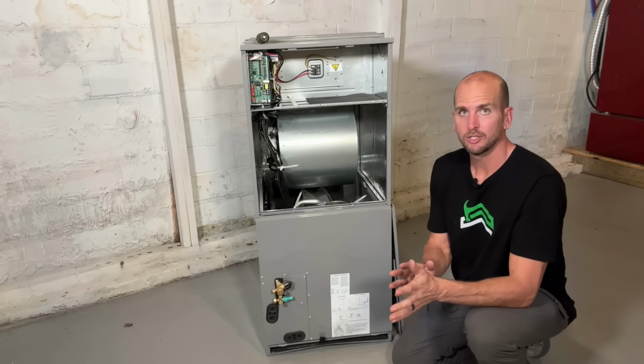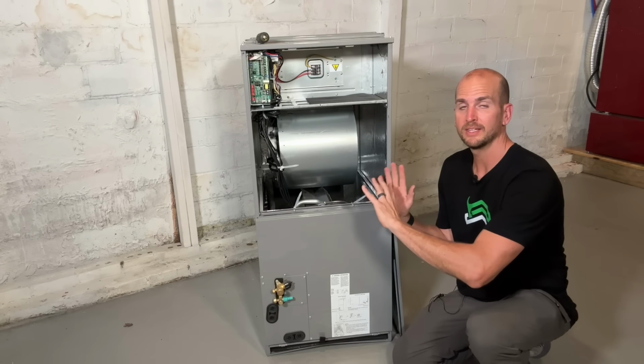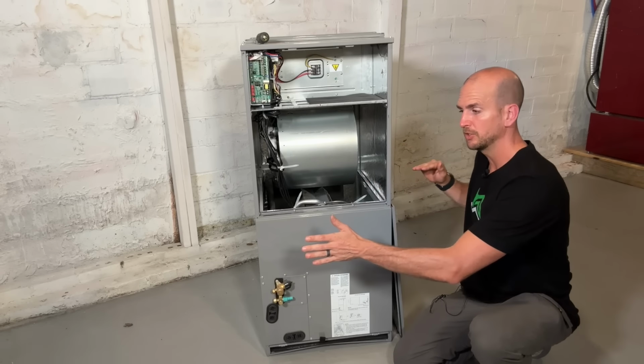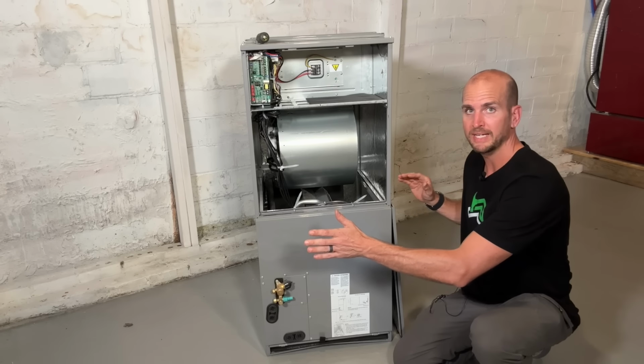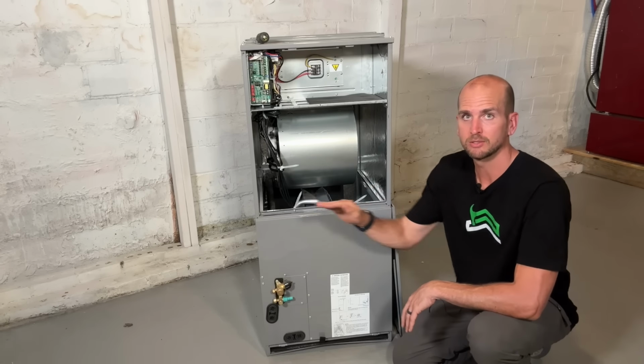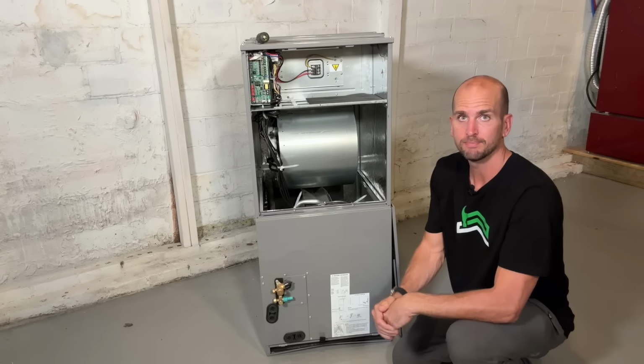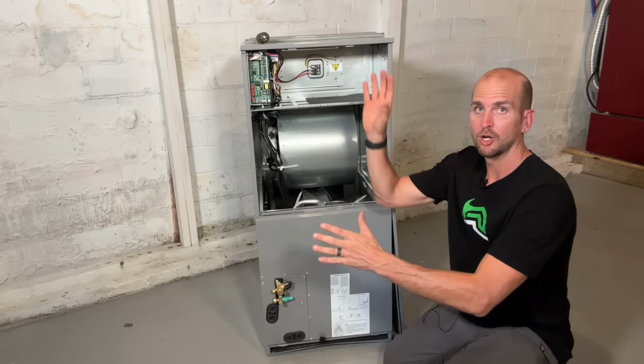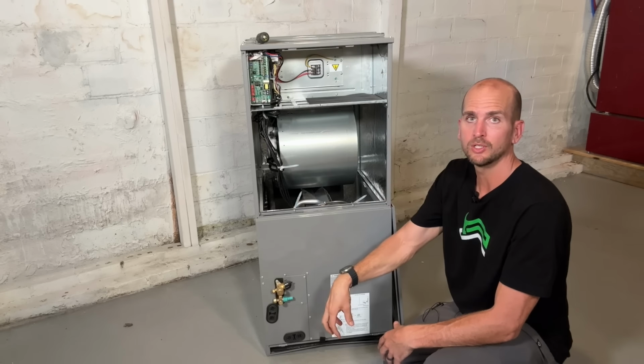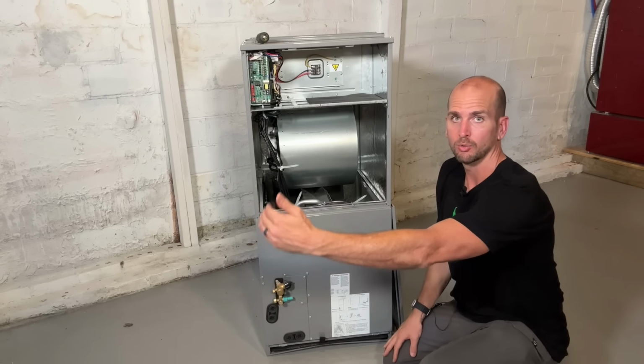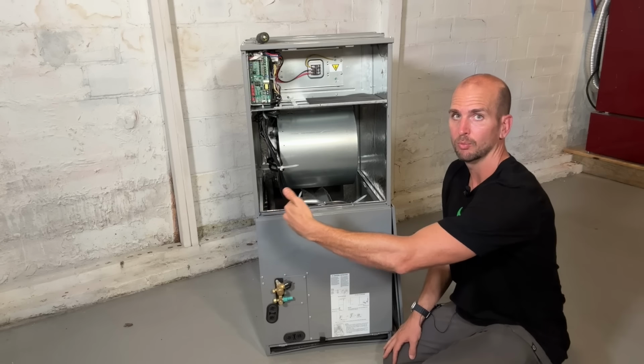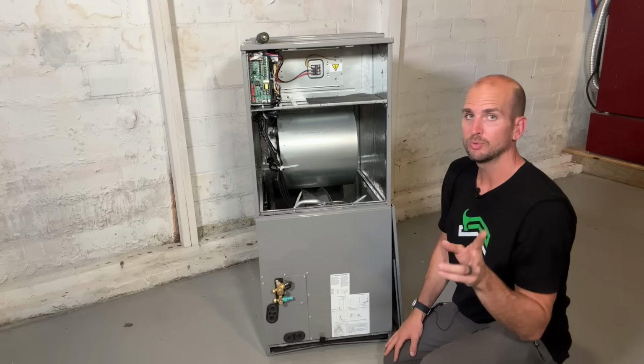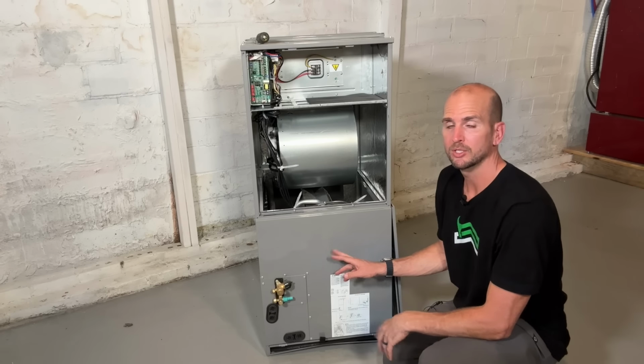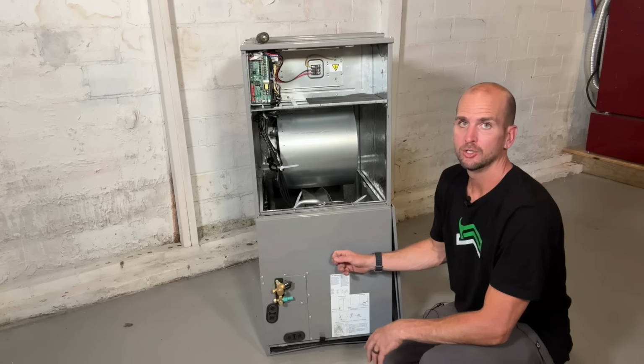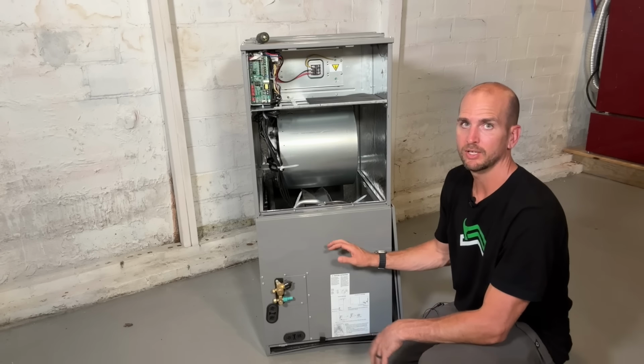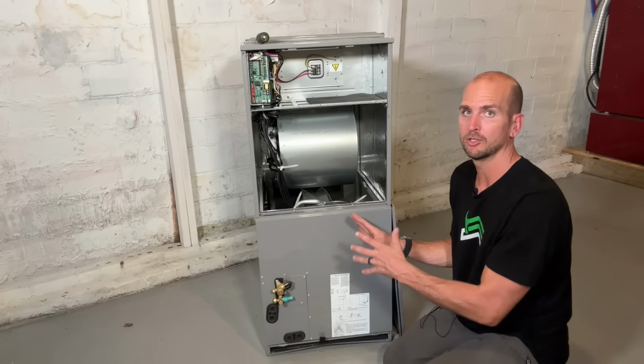Now that standard configuration will be upflow, and then if you lay it down horizontally, it'd be when your return is going from the right side and moving left. So horizontal left would be your standard configuration. If you need to, for whatever reason, go return downflow through the unit, or flip it over where your return is on the left side and moving through the right, so horizontal right, those would need reconfiguration of the evaporator. So just know that if you have that set up, you're going to have to do a little bit more reconfiguration of this unit so it's properly configured for your application.